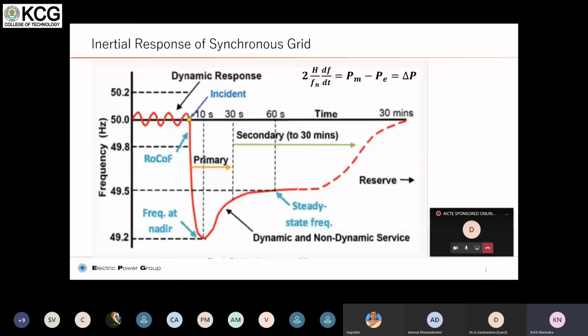We know, as fundamental electrical engineers, you need to make sure that the frequency is within a tolerance limit. The voltage must be within a tolerance limit, and the difference in phase angles must be within a tolerance limit in order for the system to always be synchronized. When the entire system is synchronized, for example, India, as of now, is one big synchronous grid because it has only one frequency of operation, which is 50 Hertz.